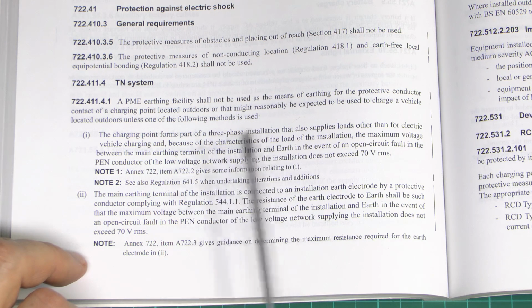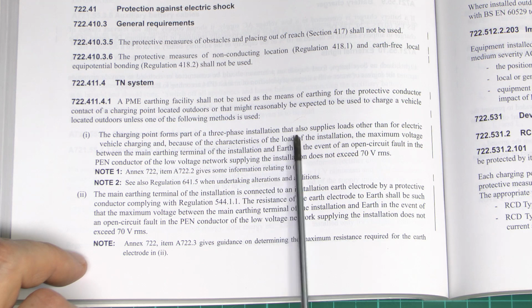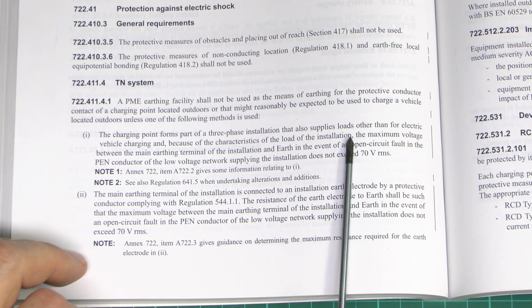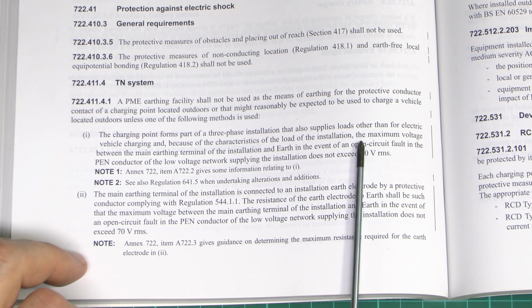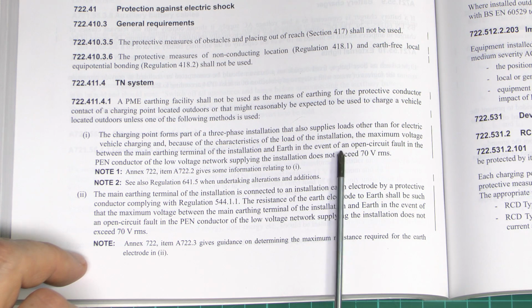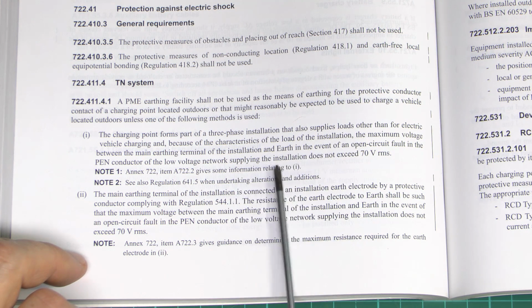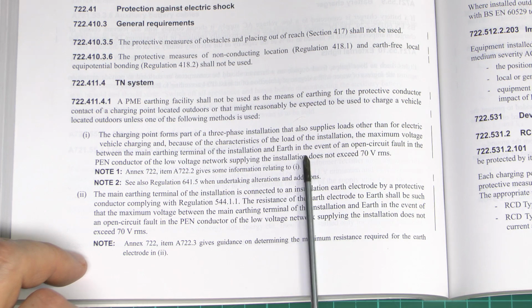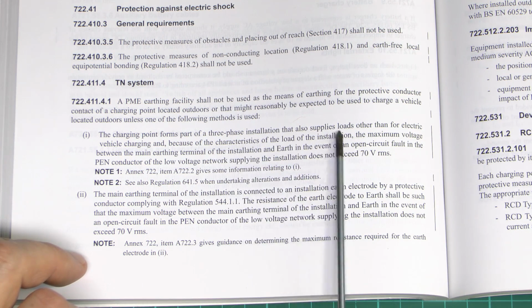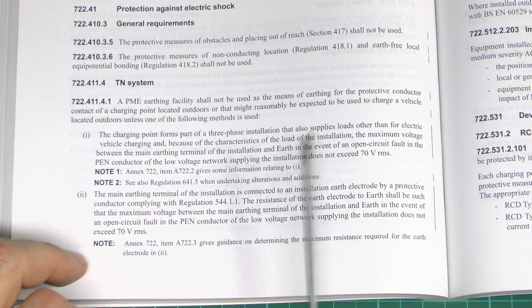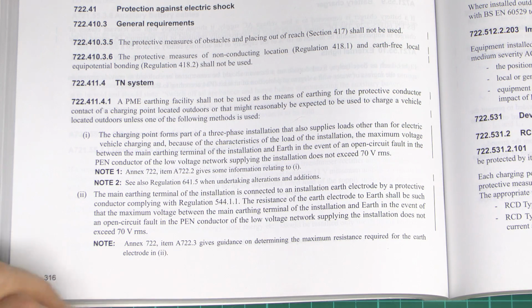So even with a three-phase installation, which you're never going to have in a domestic, it basically means that it's going to have to be a set of decently balanced loads, so things like electric motors or other three-phase loadings, and it's always going to be at that kind of stage. So unless you've got a three-phase installation with only three-phase loads connected, this is never going to apply. And even if it did, there are also other issues where the voltage could, of course, increase, say a phase dropped out or something like that. So that is never going to happen.